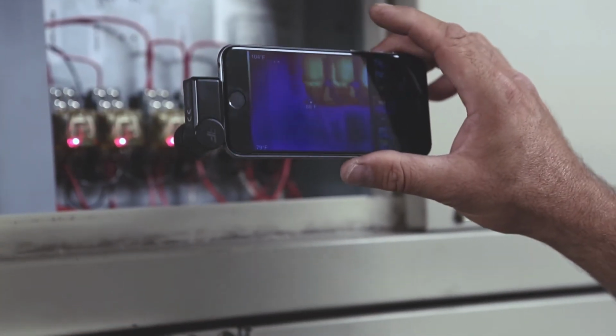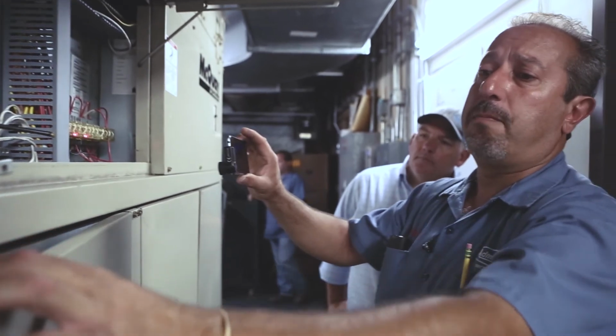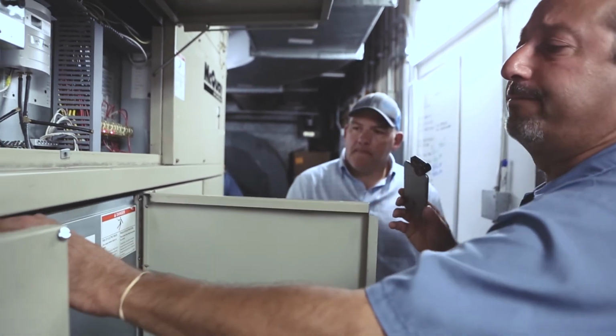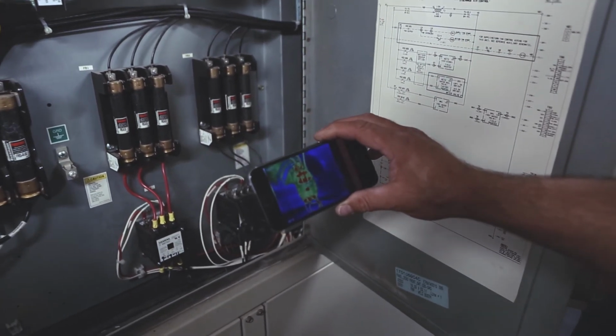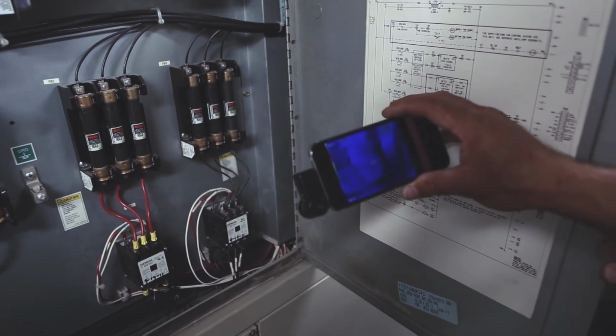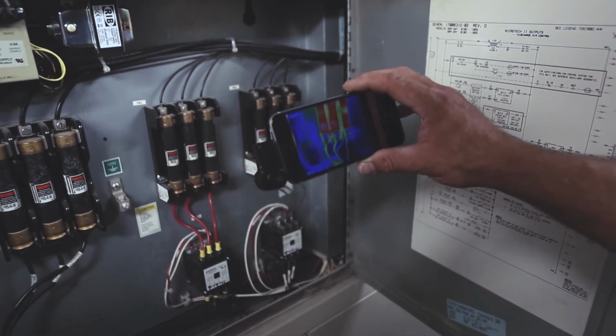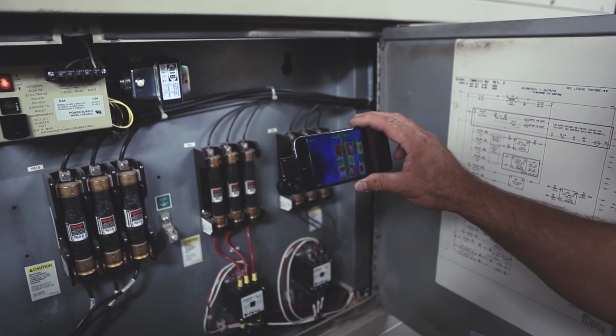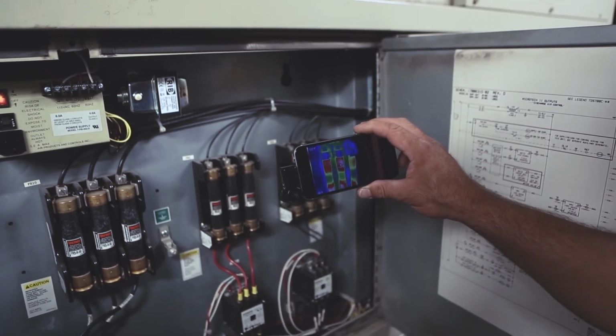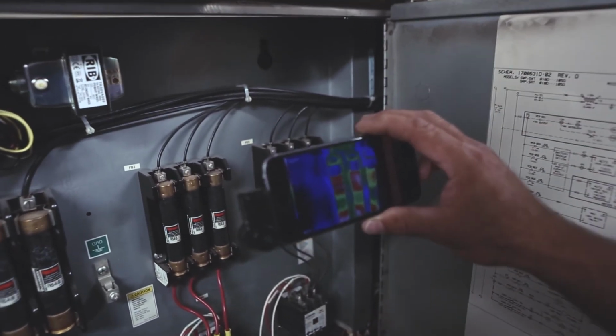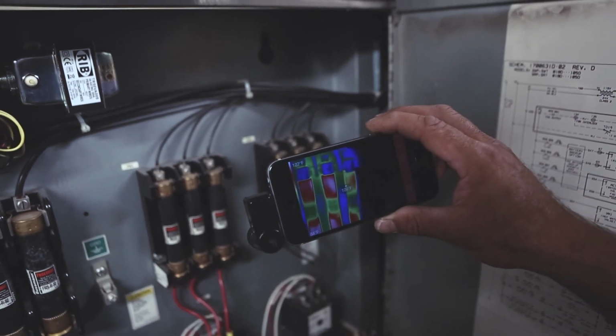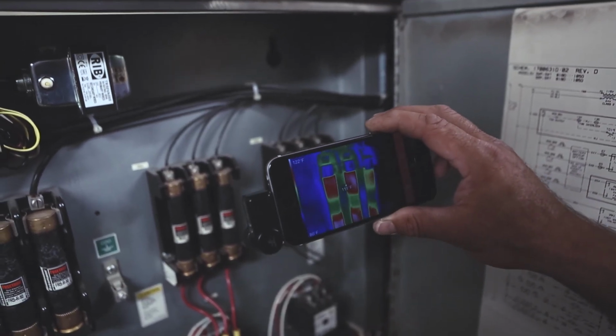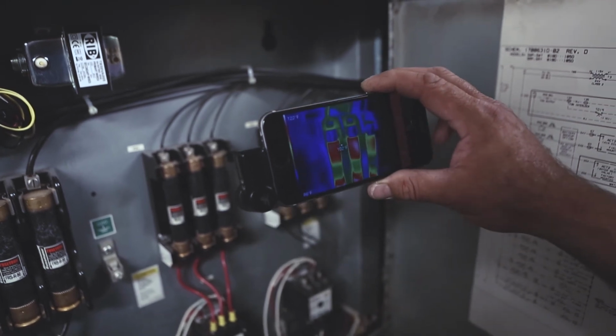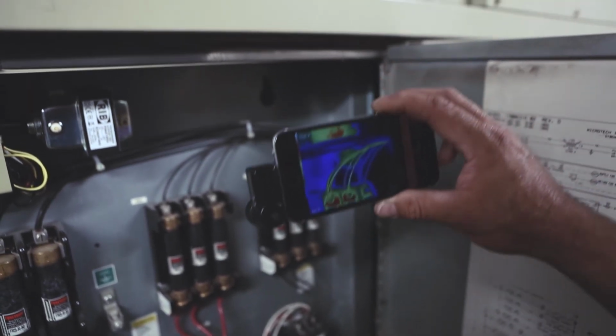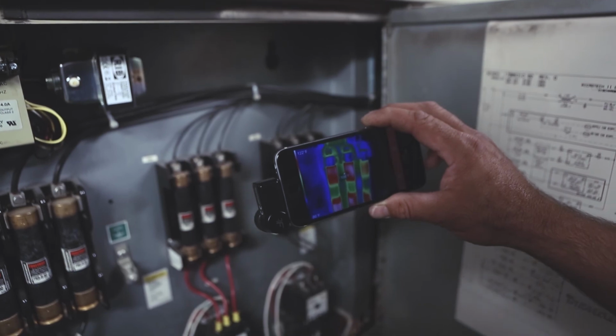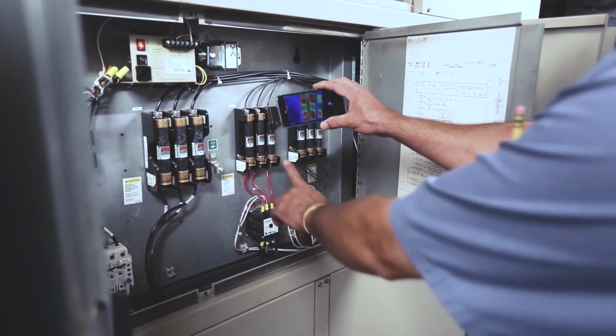It's that sensitive. If we look in the contactor panel, here's our compressor contactor running on the left, not on the right. Taking a closer look, we have 120 degrees versus 117 versus 111, a little bit of imbalance there, nothing to be concerned with as of yet, but you can definitely tell there is a difference.